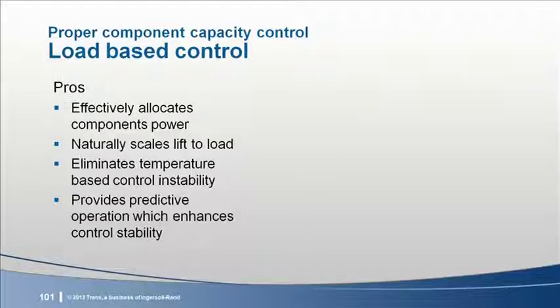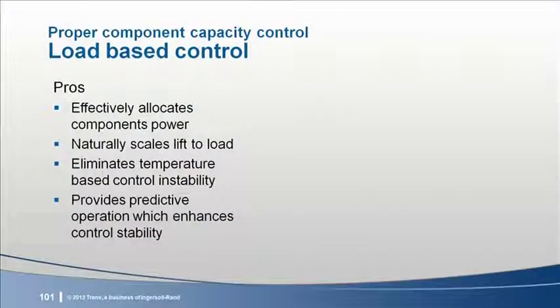The key then is proper scaling of the component operation versus system load. How is this scaling calibrated relative to full load operation? Should the scaling method be linear, or is the relationship more complex? What you find is that the answers to these questions change based on the system design parameters as well as each component's performance. The analysis is not trivial, but it's not impossible either. A secondary benefit of this method of control is that when properly implemented, it enhances control stability compared to more traditional methods.